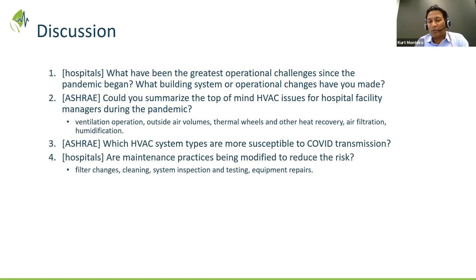The concentration can't go up. Even if it did get distributed back, it's lightly inactivated, but the dilution is quite high. That's one of the reasons why back in the spring ASHRAE was talking about increasing outdoor air rates, but now the thought process has been there's no real value to that based on the information we've found out. Filtration is important—our MERV 14 filters are definitely good enough, provided they're installed properly.